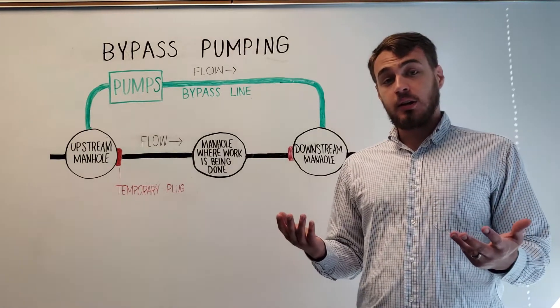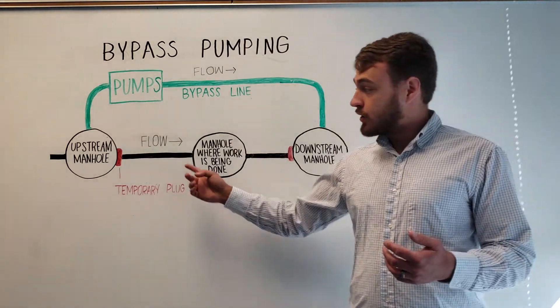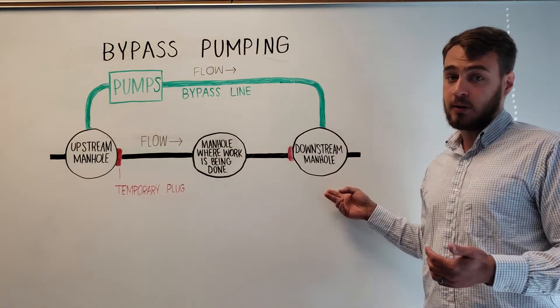So the first thing you need for bypass pumping is to stop your flows and this is accomplished through temporary plugs. One is placed in your upstream manhole which is your suction manhole and one is placed in your downstream manhole which is your discharge manhole.